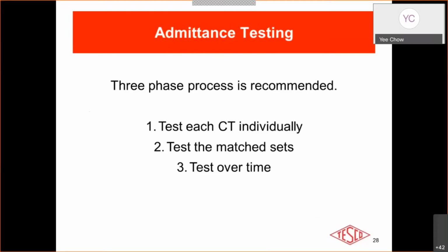So for admittance testing, we recommend a 3-step test process. First of all, test each CT individually. Optimally, it is good if you can test the CT at the time of installation. That might not be available. These could be older CTs in the field, but we recommend testing them just as soon as possible, and then testing them over time, maybe every 3 months, 4 months, 6 months, and checking the new results against the old ones to see if you have any drift. Also, if your reading gives you a short or open, you immediately know that there's some issue, not only with the CT, but with something in the secondary loop.